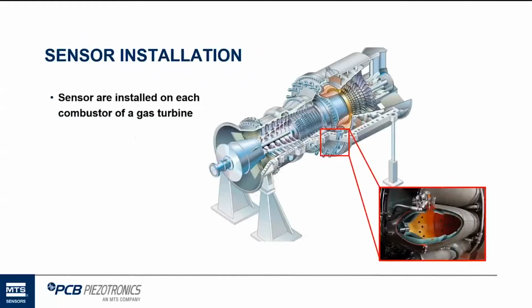So on installation of the sensors, depending on the OEM, there might be 10, 14, 16, 18, 20 combustors, but each combustor is going to have a dynamic pressure sensor, or on some newer systems made by one OEM, they're putting two high temperature dynamic pressure sensors on the combustors. So they're putting two on each. And what they're doing with the two is they're looking at different things with each sensor. One's looking at the normal stuff we're looking at, and then the second sensor is looking at some other information that they can't get from the other sensor. And it's also used, besides that, for redundancy.